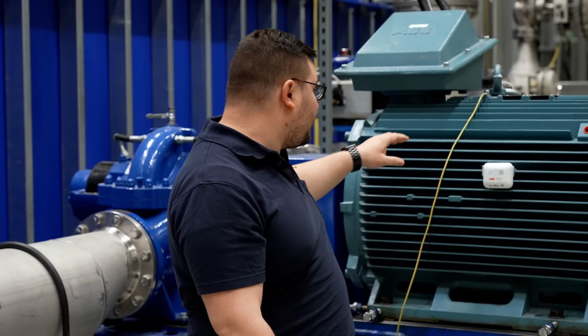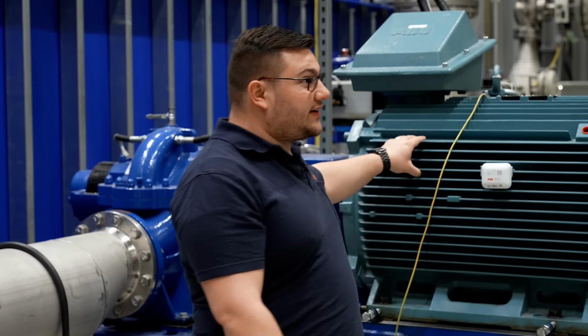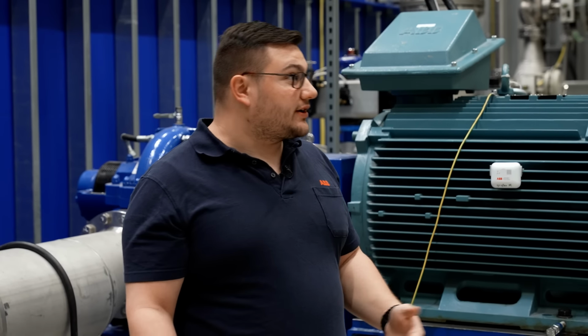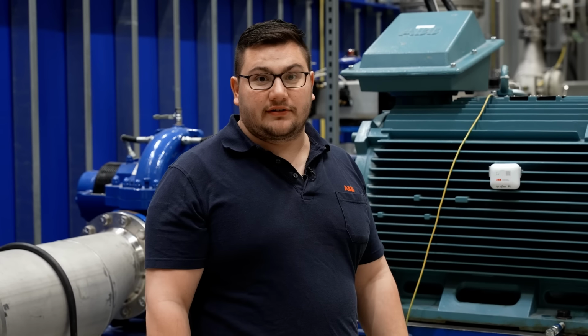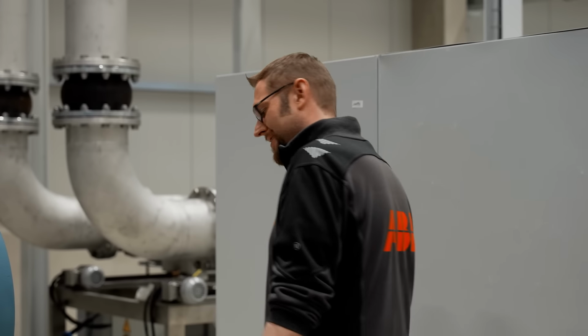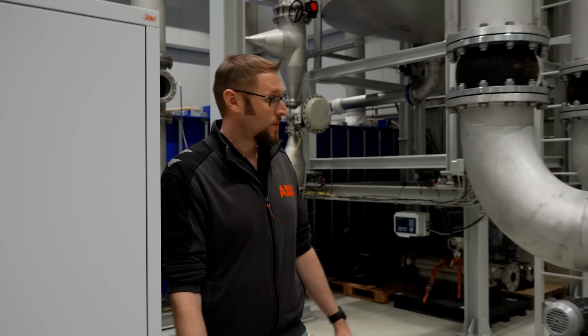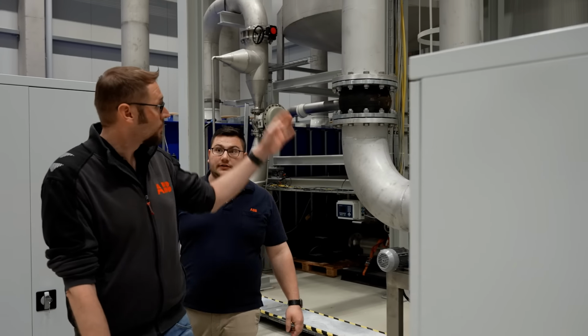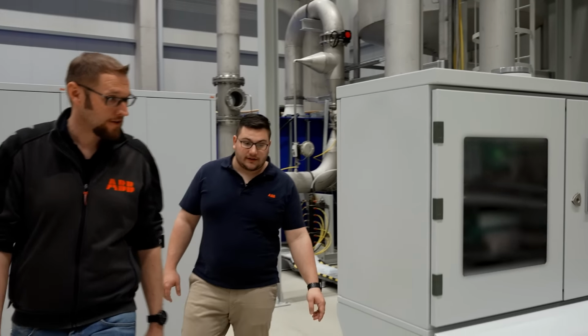Okay, do you remember last Christmas where we had such a problem with the temperature of the water? That was also due to our pump, which heats up the water faster than we expected. So we installed a bigger cooling system, and now we can ensure the perfect temperature for our calibration. But now let's have a closer look at the meter under test. So Christopher, the water comes from the top through the pipes, right? Exactly. Okay, and then here we have the meter under test.